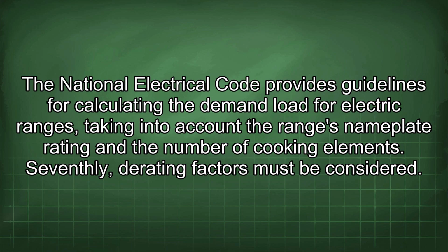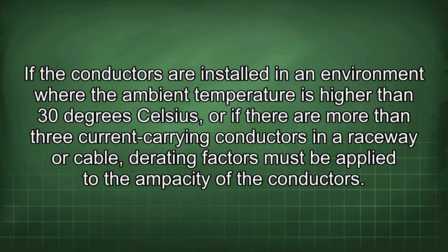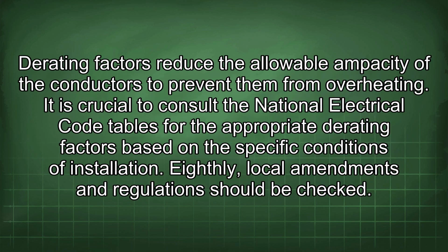Seventhly, derating factors must be considered. If the conductors are installed in an environment where the ambient temperature is higher than 30 degrees Celsius, or if there are more than 3 current-carrying conductors in a raceway or cable, derating factors must be applied to the ampacity of the conductors. Derating factors reduce the allowable ampacity of the conductors to prevent them from overheating. It is crucial to consult the National Electrical Code tables for the appropriate derating factors based on the specific conditions of installation.